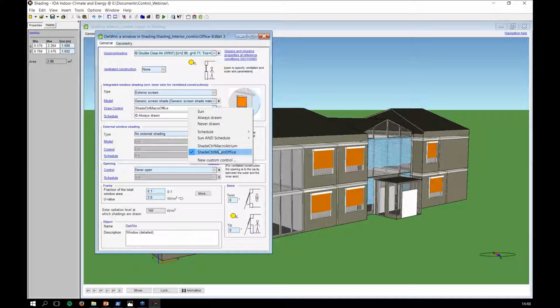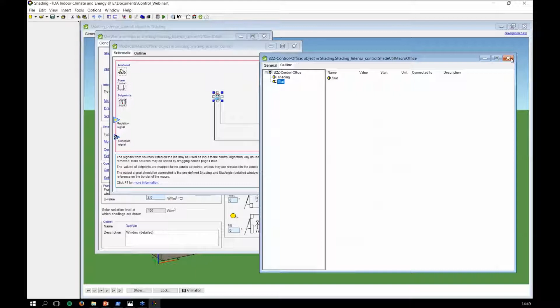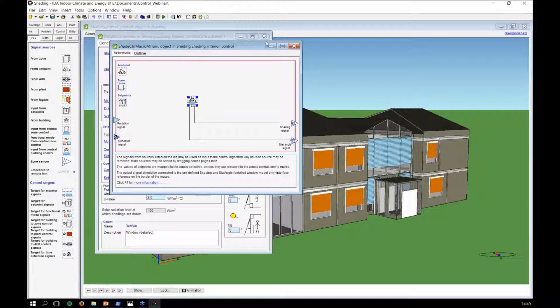There's no control structure inside. It's just an import module. This module imports the signal from the central building, from the supervisory control, to my unit, basically. If I double click this, I see the shading and slat angle interfaces that I created in the supervisory control at the building level. I'm directly linking them to my actuators, to the shading signals and control slat signals of the window. I have the same one for the atrium as well. It's just an import signal, but this one is importing from building to zone control atrium.